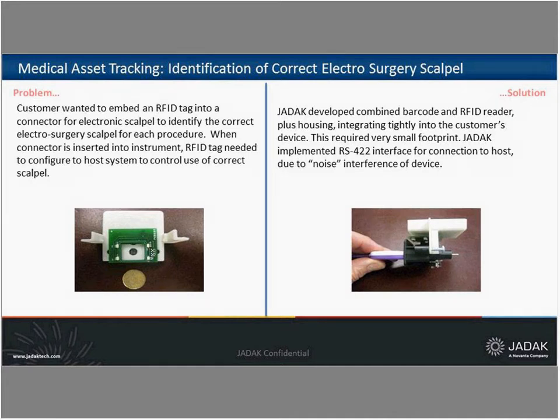Once the device was inserted and confirmed, this triggered setup of several system parameters based on which of the surgical scalpels were plugged in. They also wanted to store more data than they originally had that identified the scalpel. So not only scalpel type, but also calibration data for the specific unit. So during a refresh, they wanted to use RFID on new inserts, but still had a large population of barcoded devices out in the field.